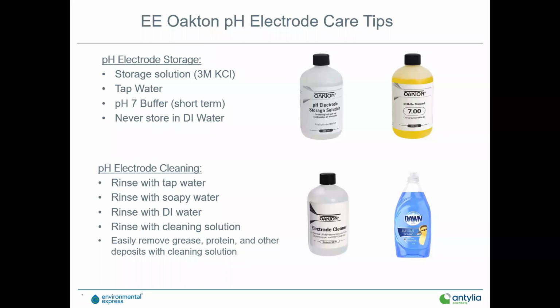So for cleaning, it's always important to rinse the electrode. If you're measuring any solutions, but especially aggressive solutions, after each measurement you want to have some tap water to quickly rinse the electrode off. The more exposure that electrode sees to aggressive solutions, the shorter its life is going to be. So rinse with tap water.